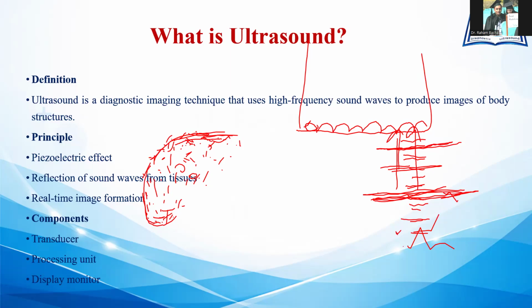Then once the echoes are reflected back by the reflector, they are received by the crystal. Initially the electric voltage was converted to mechanical energy, meaning sound energy, and then the echo reflected back towards the transducer. Now that same crystal is converting the mechanical energy into an electric signal, and that electric signal is directed towards the receiver. The receiver then processes the echo signal, enhances it, and amplifies it, and then places it in the memory. And once the entire image is formed in the memory, that is directed towards the display. So reflection of sound waves from different tissue structures is required for the formation of the ultrasound image, and this way a real-time ultrasound image is formed while structures are moving inside the body, and that movement could also be detected on the display.